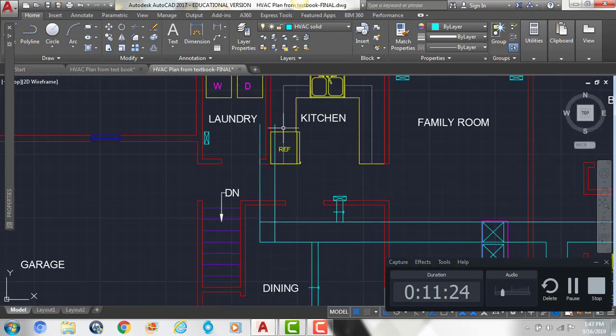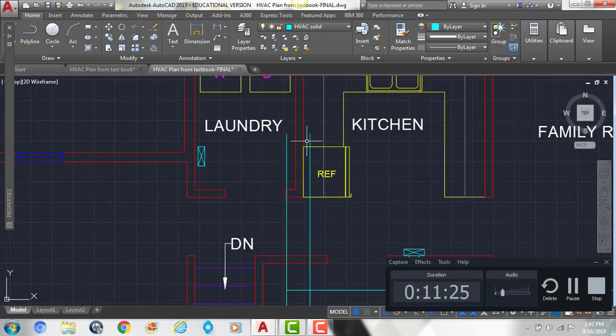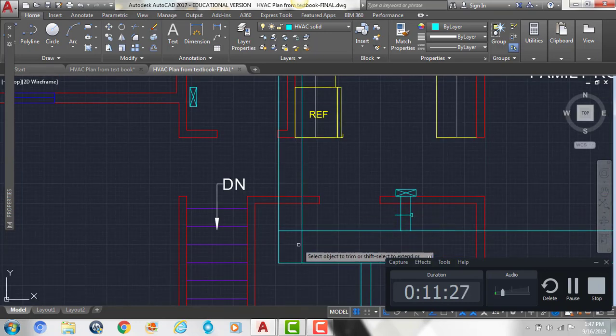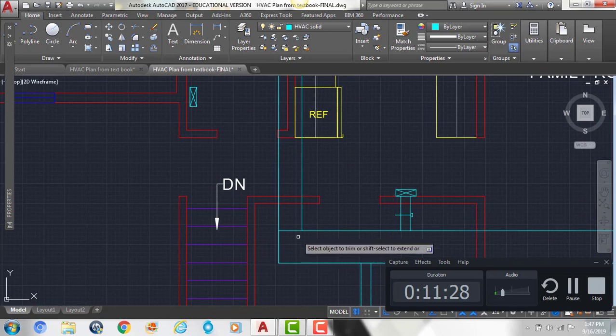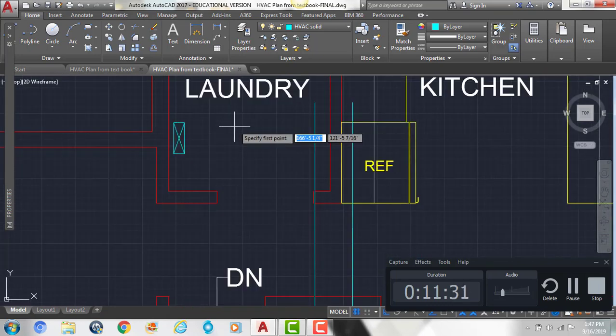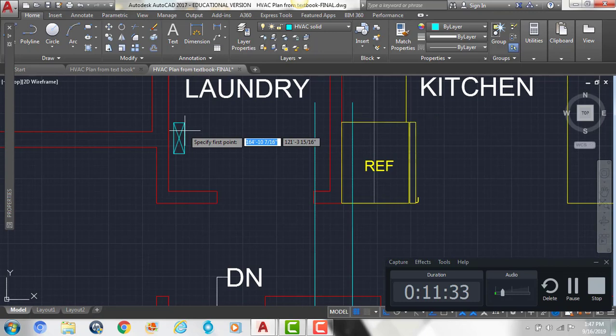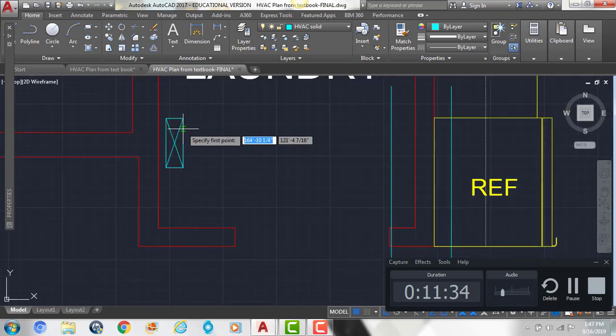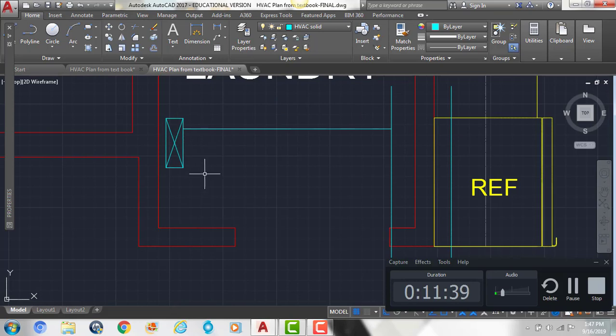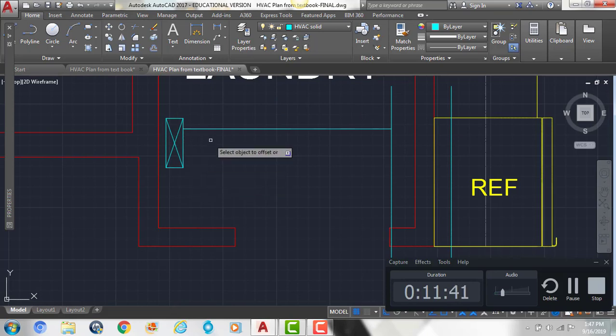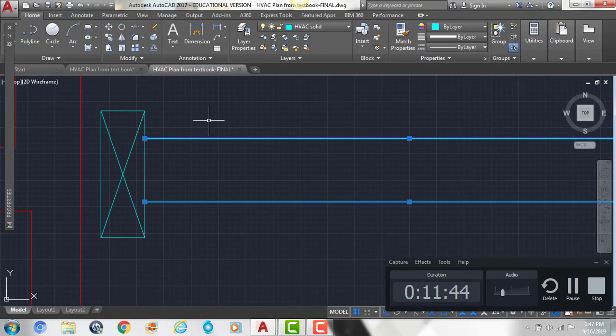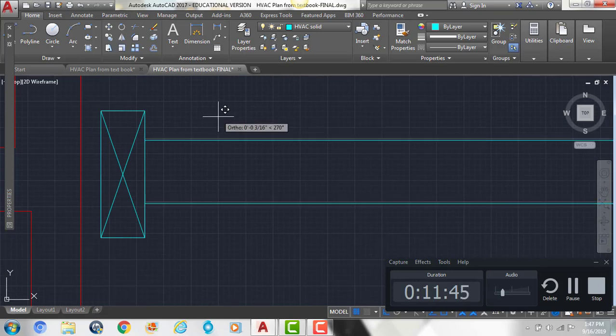And then we're going to do the same thing we did with the other one. We'll trim out that corner. And then we're going to draw our 6 inch duct that goes to the register. So we're going to offset this by 6 inches. Make sure it looks centered.